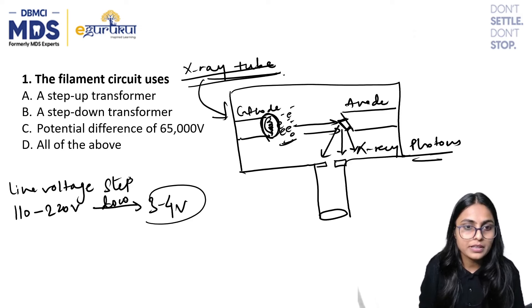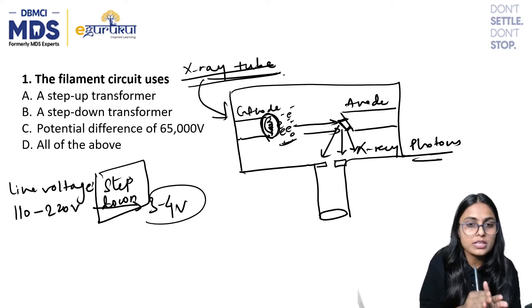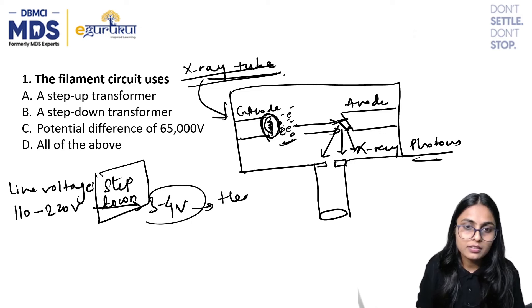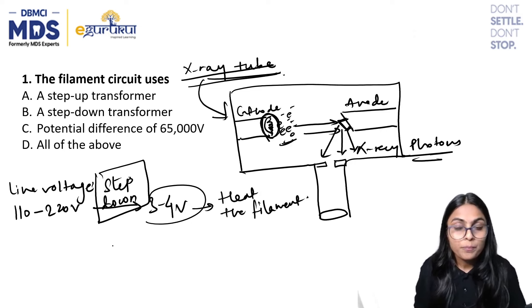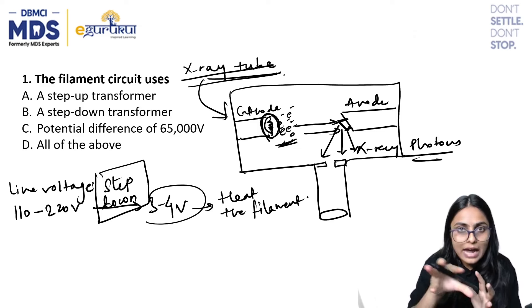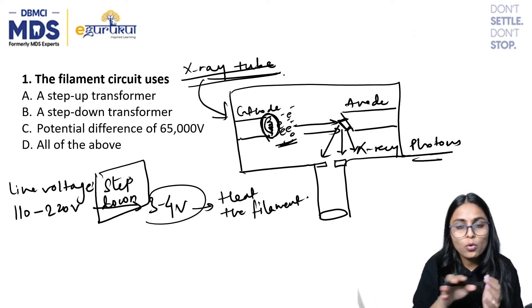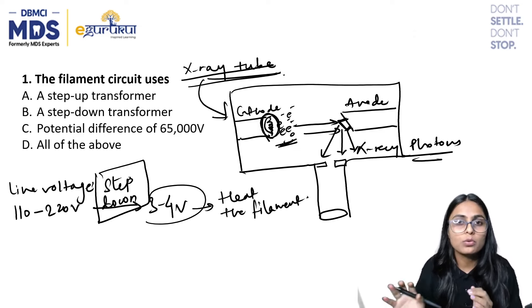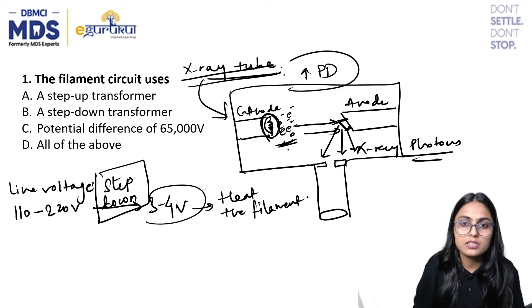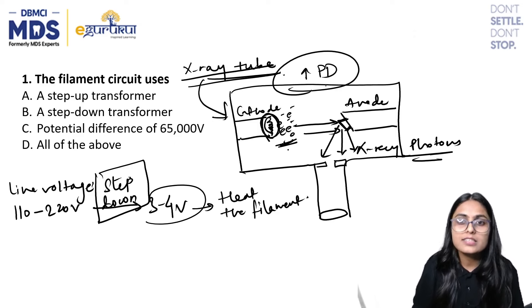As the name suggests, the step-down transformer reduces the line voltage to 3 to 4 volts, and this is required to heat the filament. After formation of the electron cloud, we need to give kinetic energy to it so it bombards the tungsten target. This is done by increasing the potential difference.